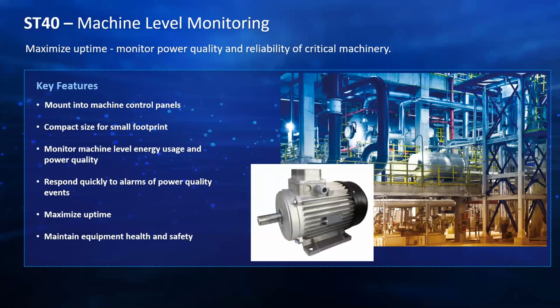We can monitor voltage. Any sort of voltage unbalance will significantly reduce the life of a motor. We can record that information. We can set up limits. So with the SCADA system, you can be alerted anytime there is voltage imbalance on this motor. So you can start to take the steps to correct those imbalances to improve the life of this motor.